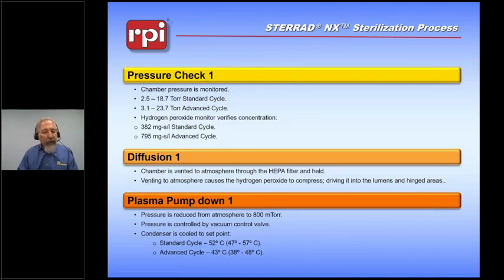We allow the material to sit in the chamber, and we allow air to flow into the chamber to let the hydrogen peroxide diffuse into the very smallest places within the instruments that are contained within the chamber. That diffusion step spreads the hydrogen peroxide into every possible place that it needs to reach. And once it's uniformly spread, we allow air into the chamber through the venting, and that air forces the diffused hydrogen peroxide into every space that is no longer under vacuum. That's what does the full diffusion through all the lumens and through all the hinges.